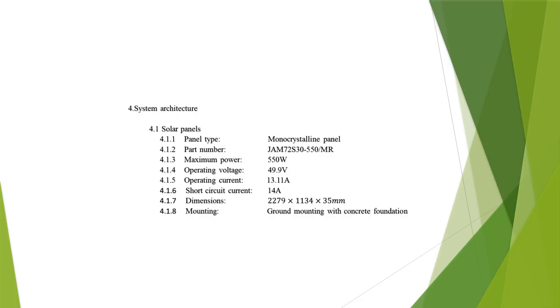On system architecture, we've got solar panels, and the chosen panel type will be a monocrystalline panel with a type number of JAM72S30-550/MR with a maximum power of 550 watt, operating at a voltage of 49.9 volts and operating current 13.11 amps, short circuit current 14 amps, and the dimensions 2279 by 1134 by 35 millimeters, and to be ground mounted with concrete foundation.